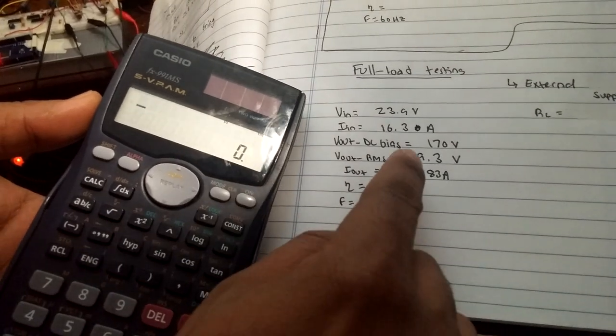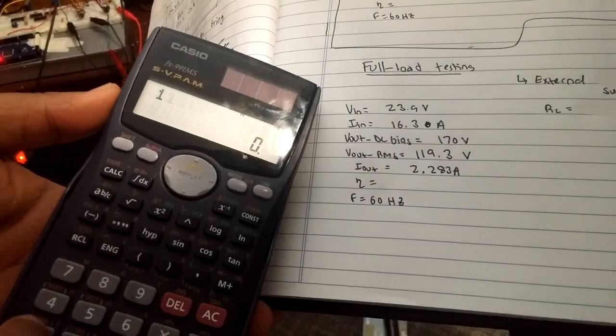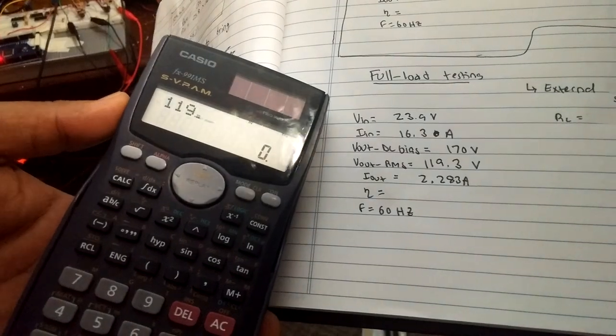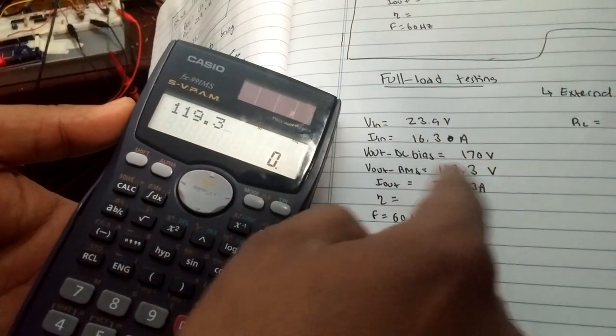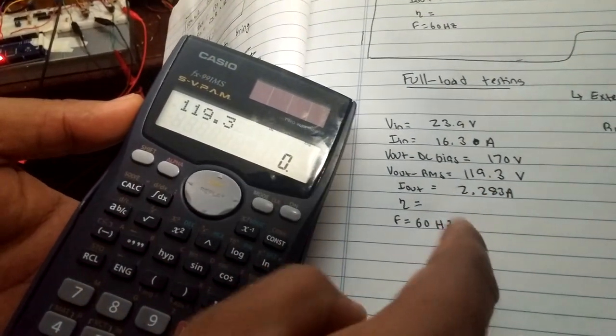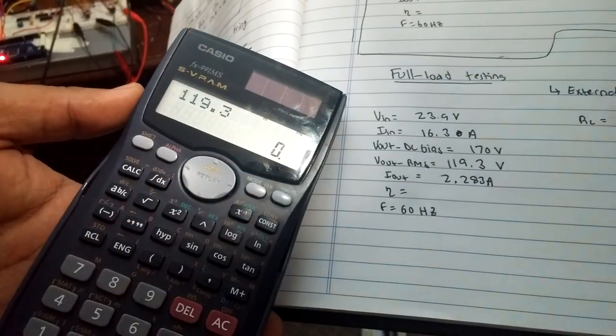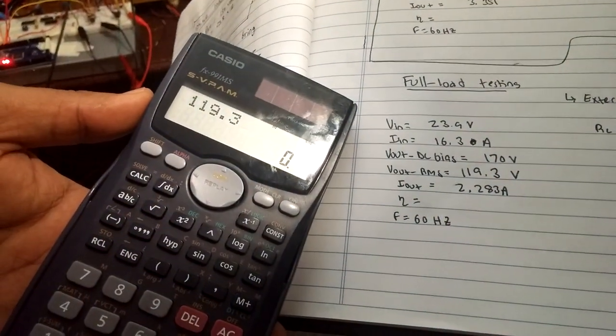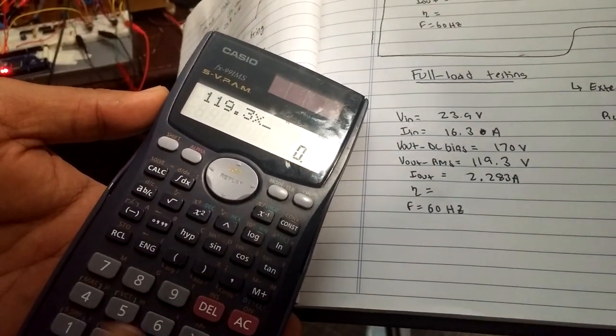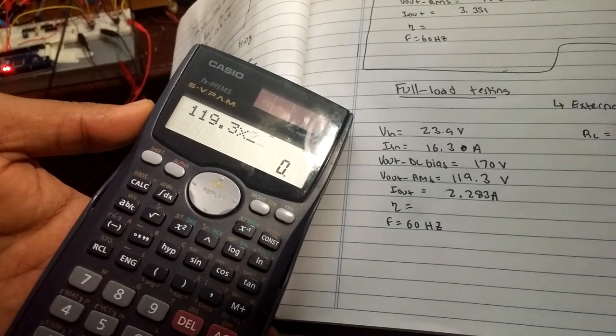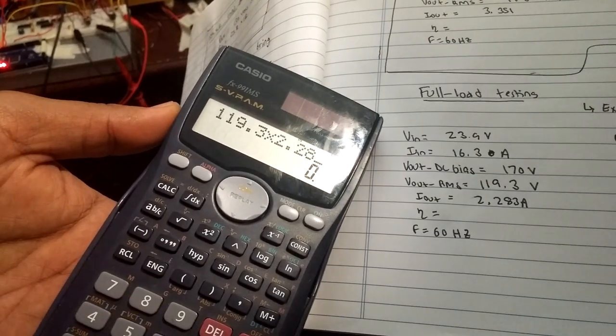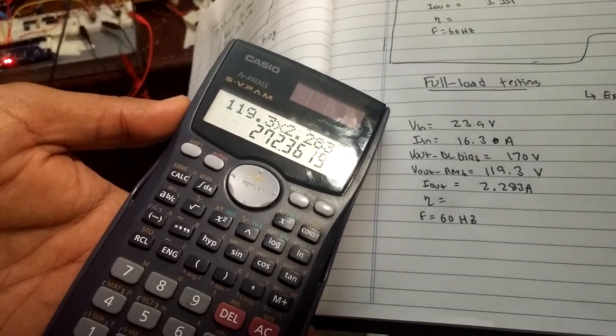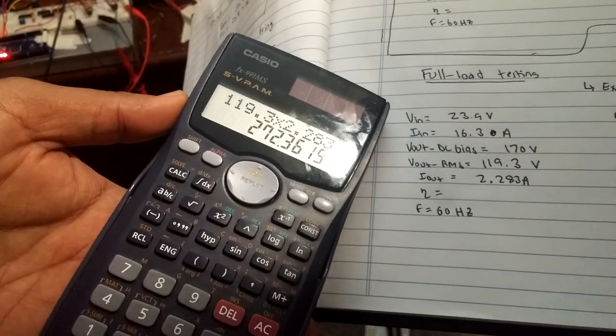So our output is 119 volts multiplied by, since it's resistive load, no power factor comes into play here, so we'll just do current multiplied by voltage. That should give us our output power. So 2.283 amps, output power is 272 watts.